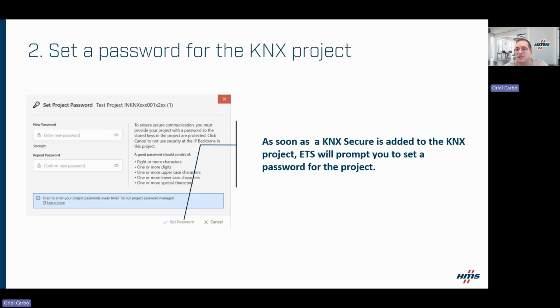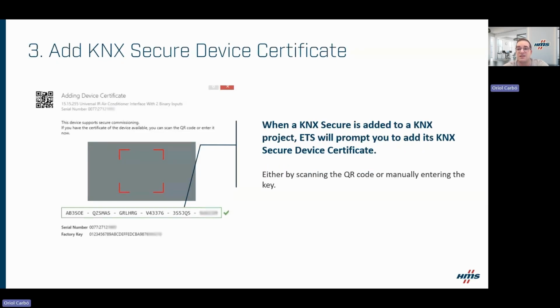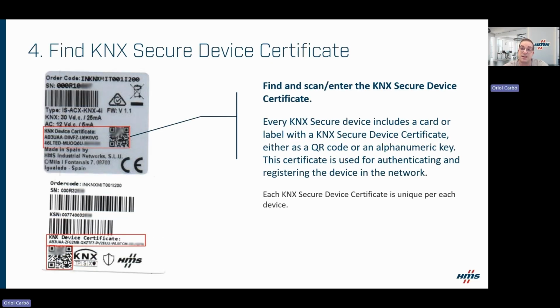As soon as you add the KNX secure device to the project, ETS prompts you to set a project password. This is required to manage the secure commissioning workflow. Then ETS will prompt you to add the KNX secure device certificate. You can do this by scanning the QR code or entering the key manually. Each KNX secure device includes a certificate card or label with the QR code or an alphanumeric key. This certificate is used to authenticate and register the device in the network. And more important, each certificate is unique per device.